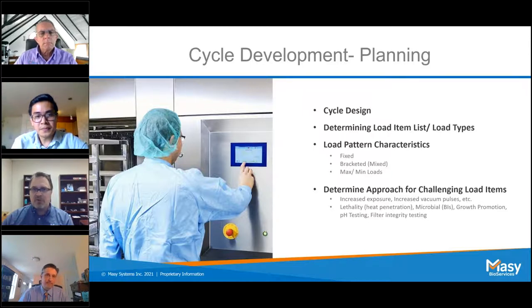The other larger category I mentioned is liquids. Those are, as Rob said, your agars, your broths, your media, sterilization of those liquids. And that often involves the use of a load probe that's actually placed in a liquid, so it controls the cycle a little bit differently. So there's actually a different cycle with different parameters that are involved there. And also it's a little bit longer. It takes longer because you can have the result of having everything splatter everywhere if you change pressure too quickly while you have the hot liquids in the chamber. And it also typically doesn't involve that pre-vacuum conditioning that the other items did. And then sometimes there's oddball items that go in there, and you just have to really understand what you're trying to achieve with that particular item, a filter, for example, and design the cycle for that appropriately.